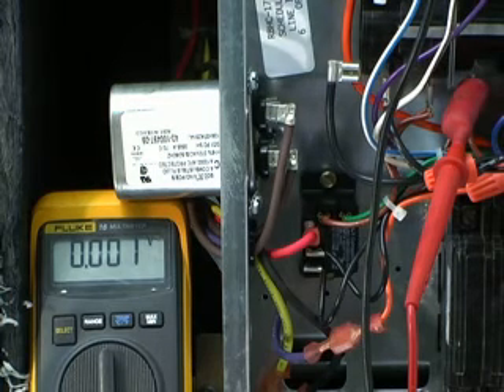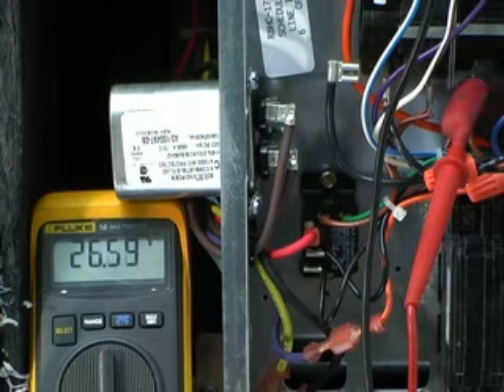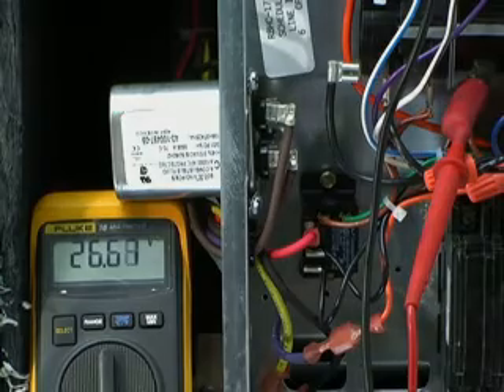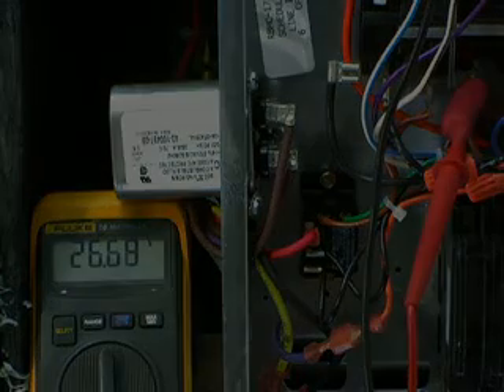Now if you get up there and it's running and you read voltage, then you've got to start backing up towards the thermostat and see where you're getting your voltage from.